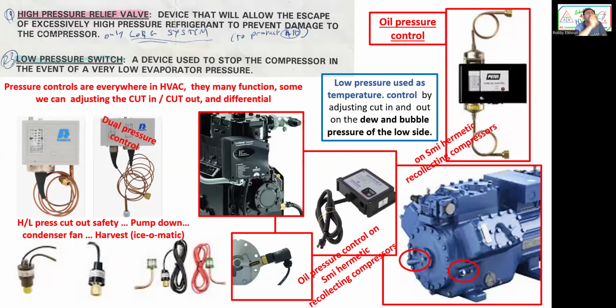So the pressure controls are everywhere in HVAC. They have many functions. Some we can adjust the cut in, cut out, or cut in and differential. A whole class about pressure control adjustments. There are high and low pressure safety. They use them for pump down or pump out. And they use them as condenser fan on and off to control subcooling. And they're used in some ice machines for harvest, and the Ice-O-Matic ice machines. They have many functions. Low pressure control is also used as a temperature control.